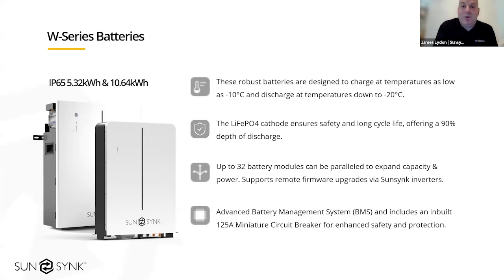Again, full LiFePO4 on the W series with a 90% depth of discharge. And we can have up to 32 of these connected in parallel, so it gives you, again, an idea of the scalability. Also on the W series batteries, we have a built-in 125 amp MCB, so that will save extra installation work in adding extra isolation. And the W series are available in 5.32 kilowatt hour and 10.64 kilowatt hour modules.